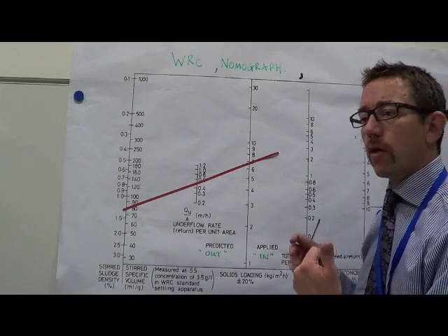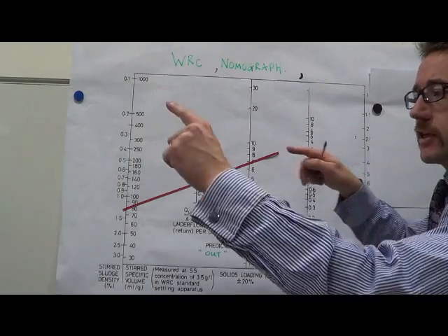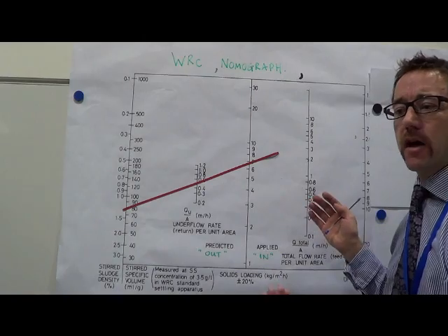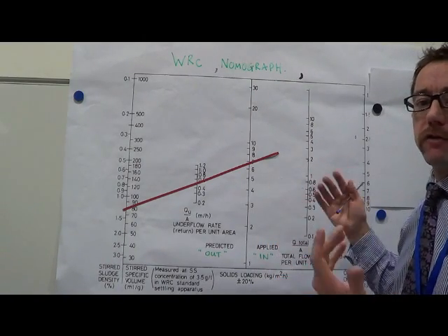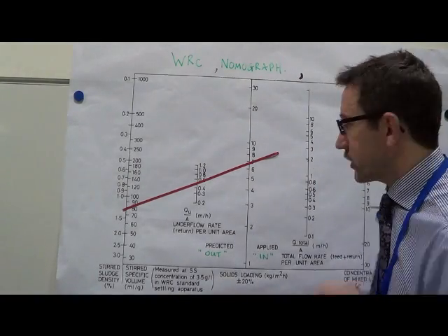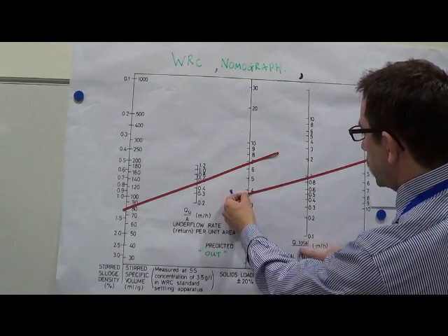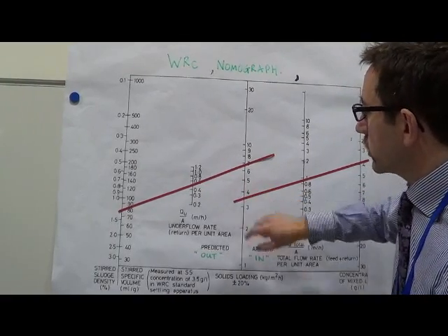So this is the total of, if you remember in our diagram before, the return rate plus what's coming in. And given that we're looking at the worst case scenario here, we're always interested in storm conditions, so at flow to full treatment. So similarly, you'll get your work out for your site: what's your mixed liquor, what's your total flow divided by your surface area, and it'll say how much solids am I trying to put onto my tank.